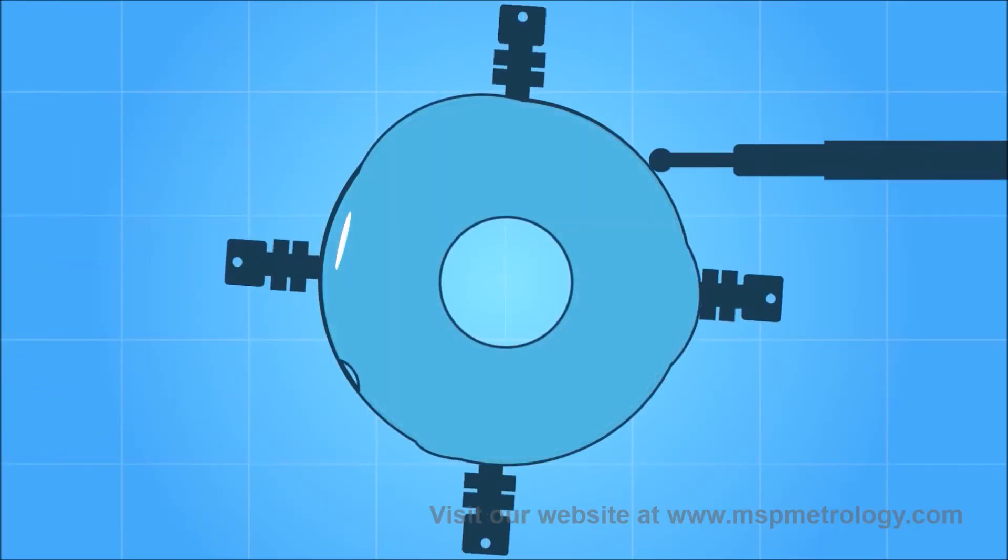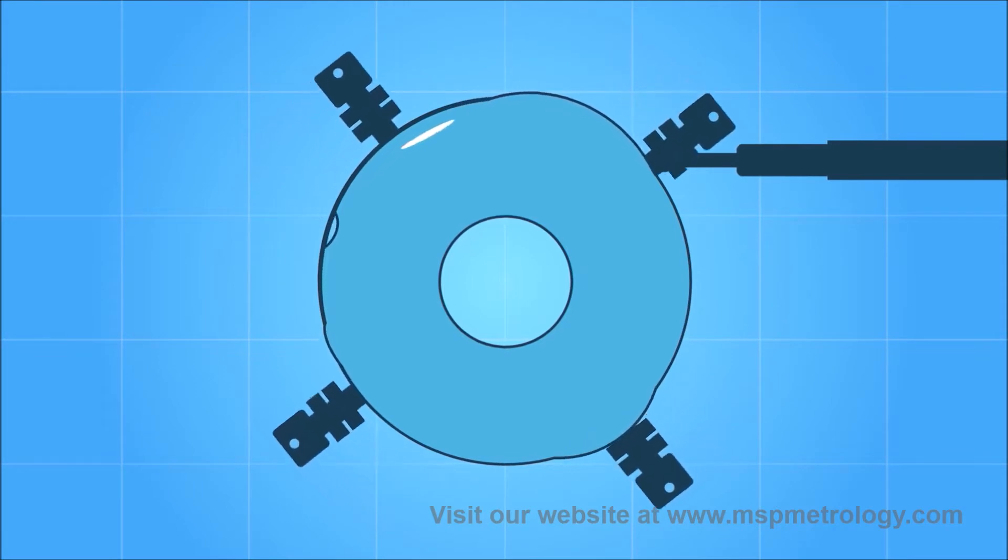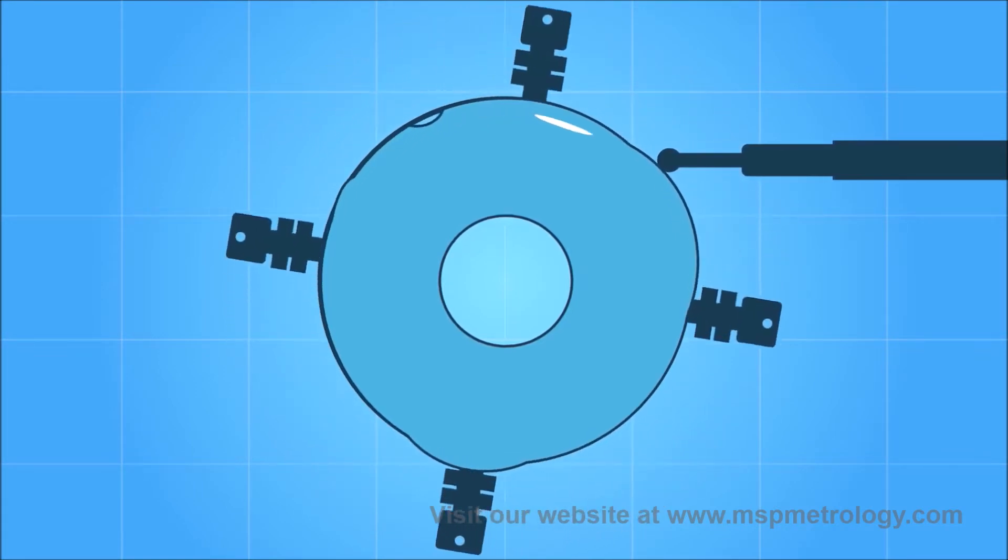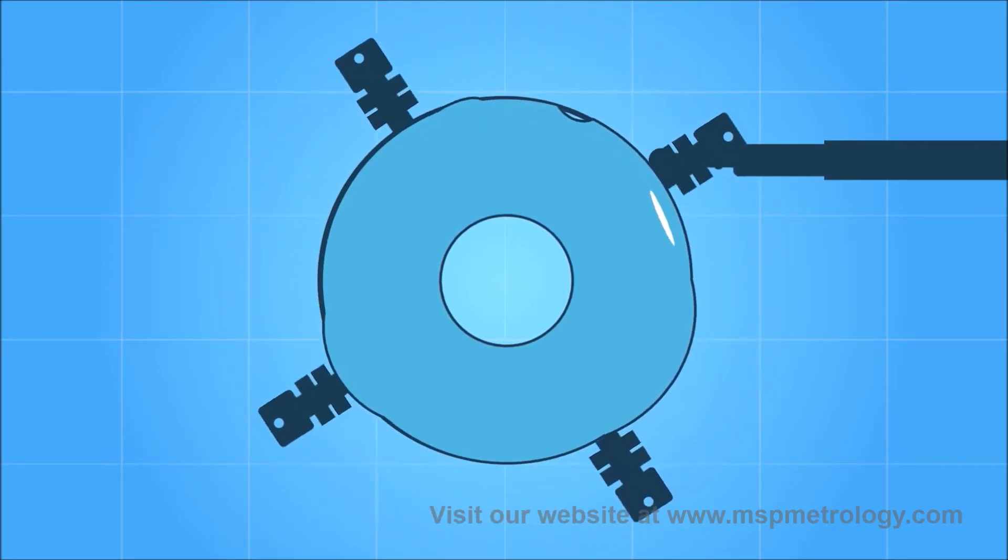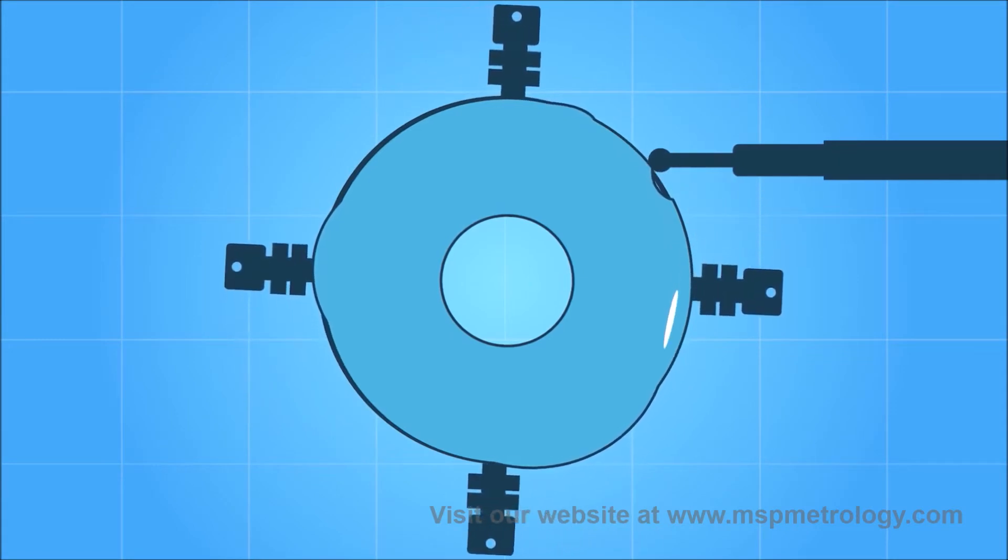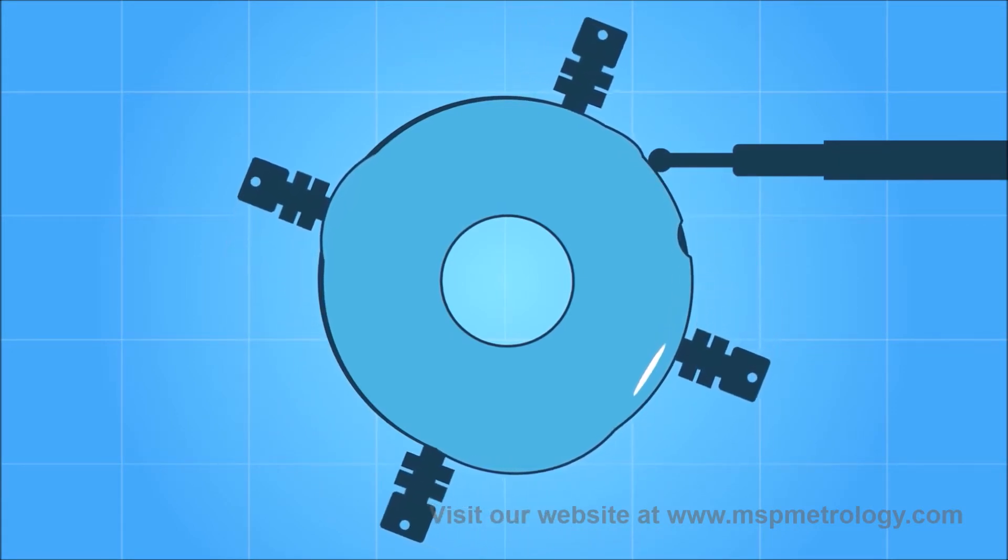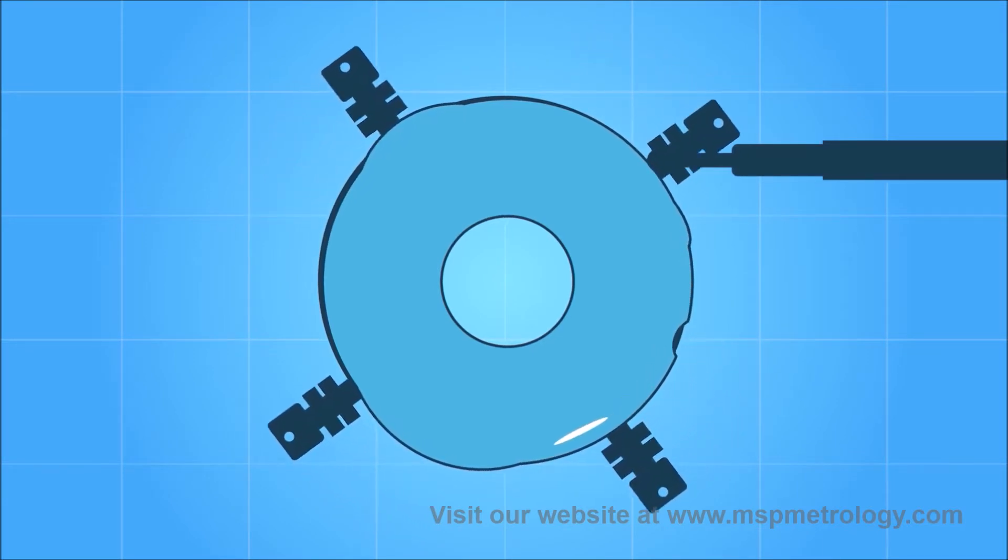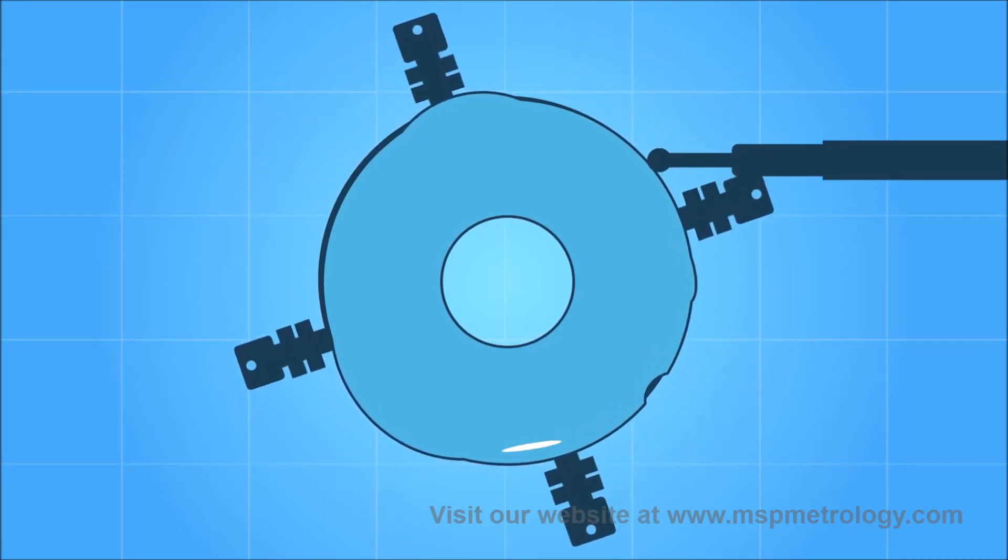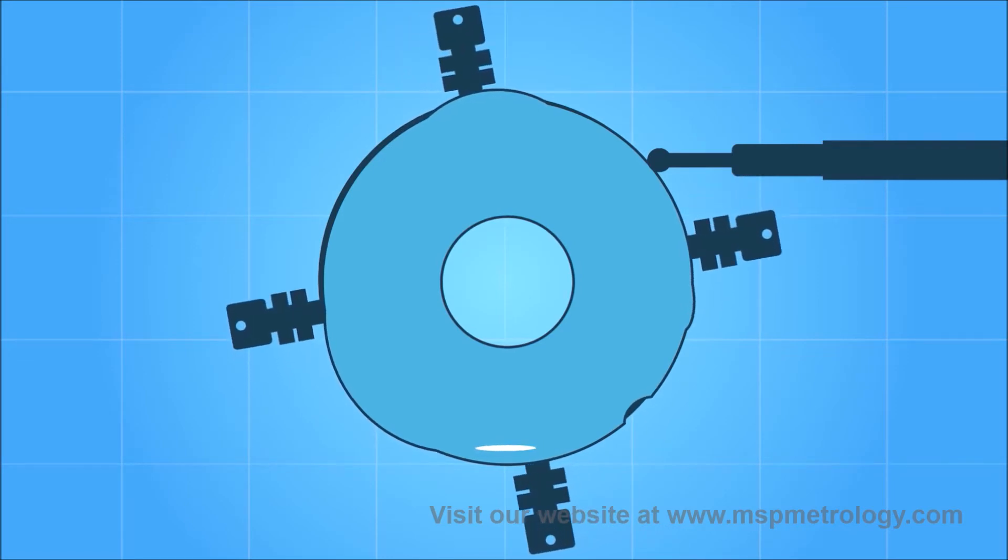During rotation, a transducer measures radial variations on the surface of the part with respect to the spindle's axis. Limited only by the precision of the spindle and transducer gauge head, the extrinsic datum method can be used for the most extreme roundness specifications and parts with complex surface features.